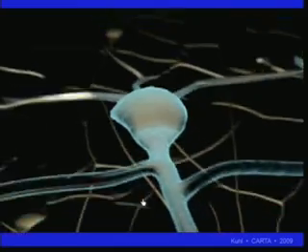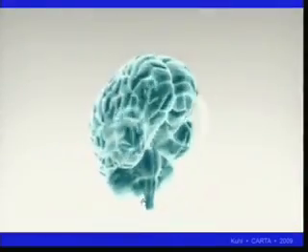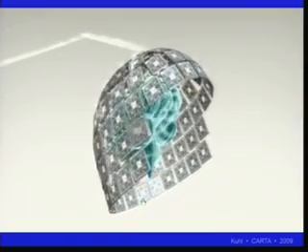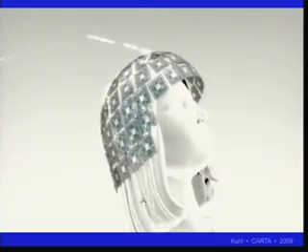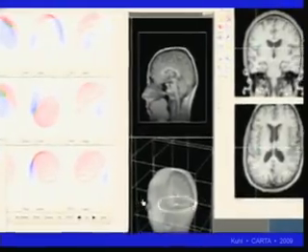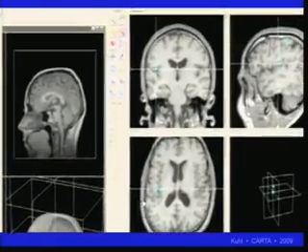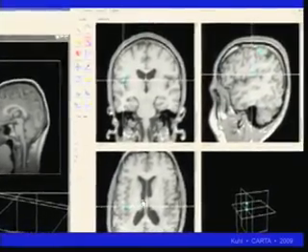But it is a completely non-invasive, totally safe measurement tool that, with sensors in the dewar, it looks like this hairdryer-type device, is picking up the activity of millions of neurons working together, which emit a magnetic field that changes as neural activity goes forward. And so as you sit in the hairdryer, the 306 sensors pick up the activity and can plot with millisecond accuracy, that's the advantage over fMRI, and millimeter spatial localization capacity. Now, we're very excited about this, not only because it's non-invasive, noiseless, so unlike fMRI, it's not producing any noise, but here's what's fun.